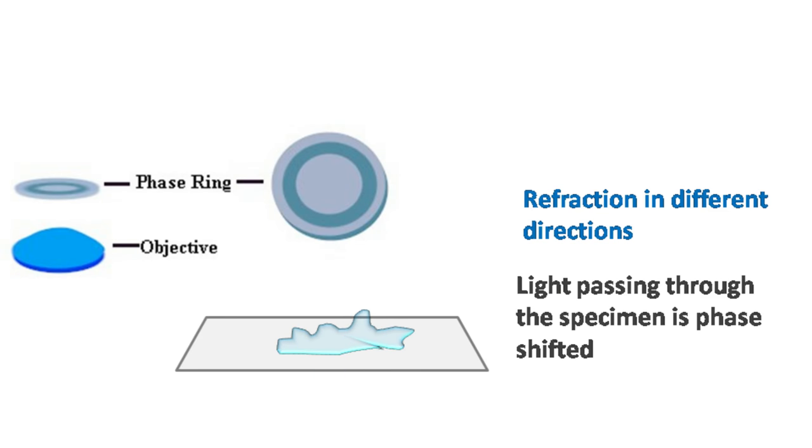If the refracted light hits the phase ring in the objective, the phase shift of the light increases and that region of the specimen is seen as dark. If the refracted light fails to hit the phase ring, then that region of the specimen is seen as bright.